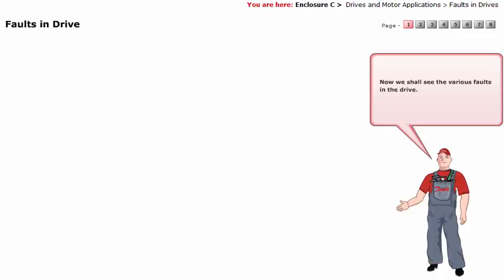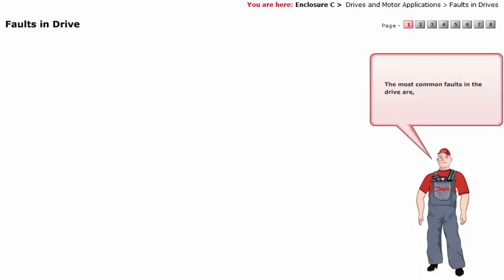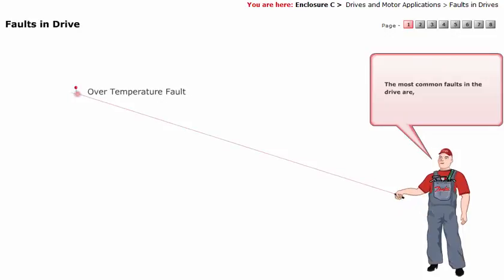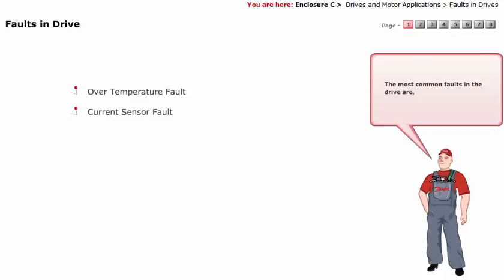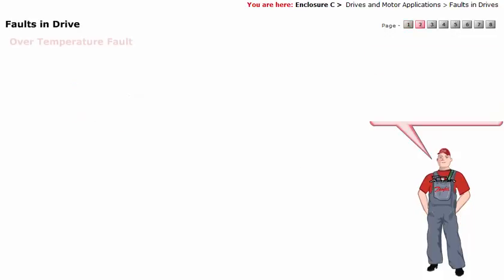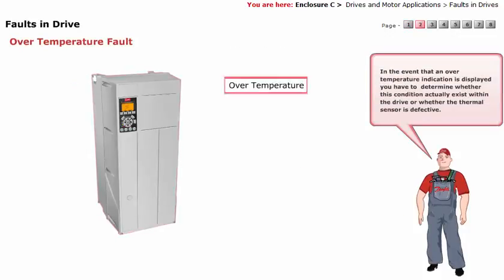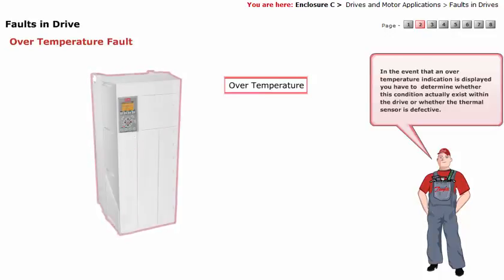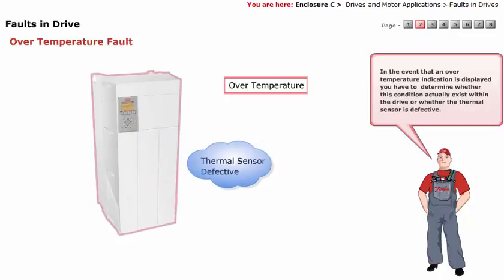Now we shall see the various faults in the drive. The most common faults in the drive are over temperature fault and current sensor fault. In the event that an over temperature indication is displayed, you have to determine whether this condition actually exists within the drive, or whether the thermal sensor is defective.